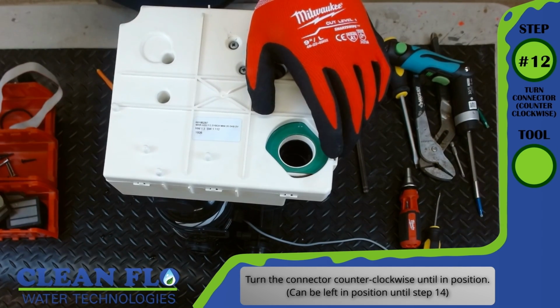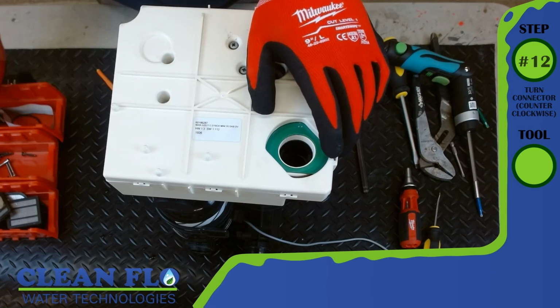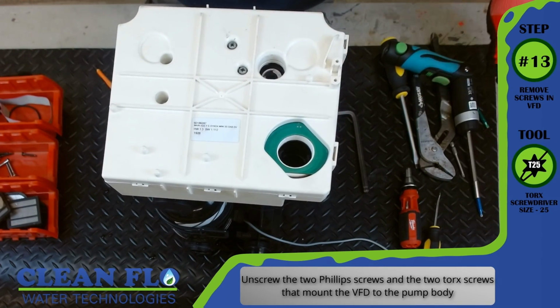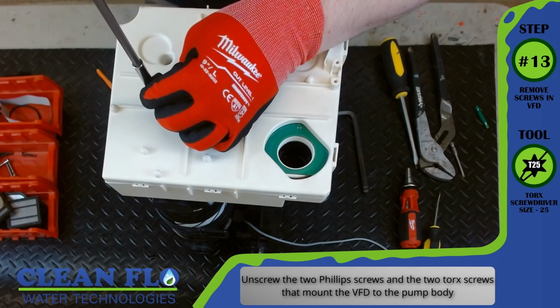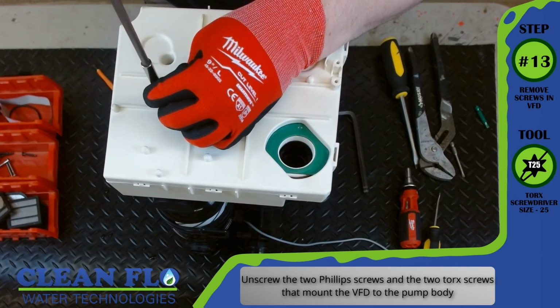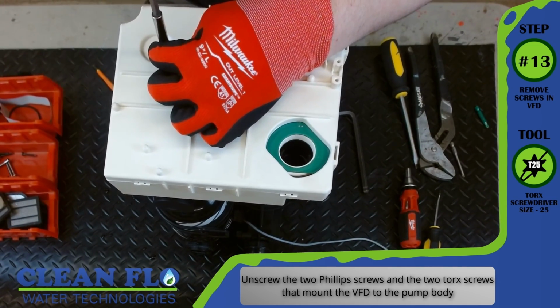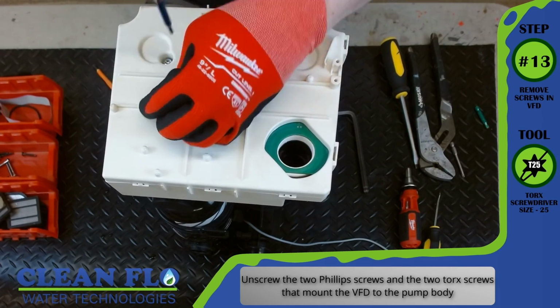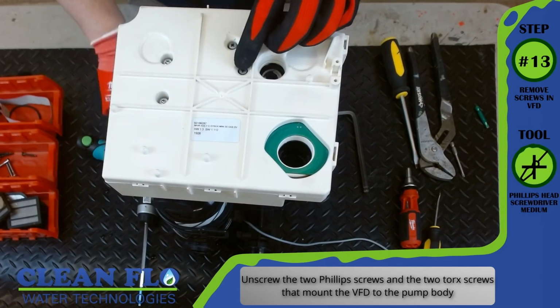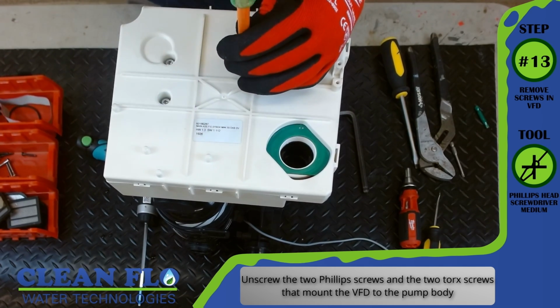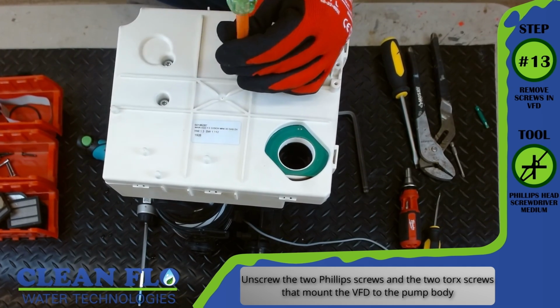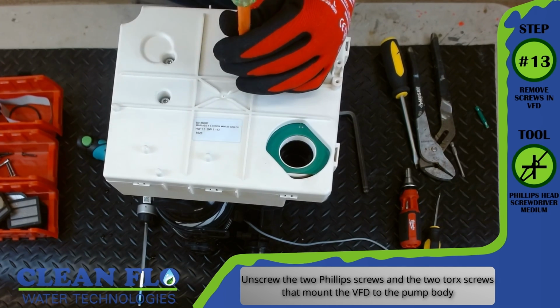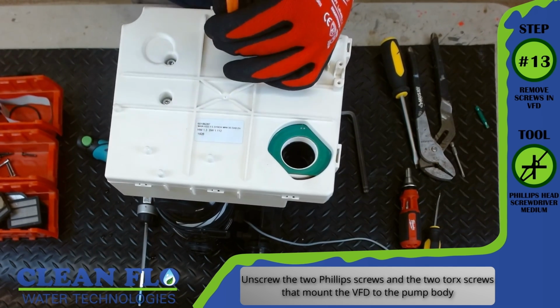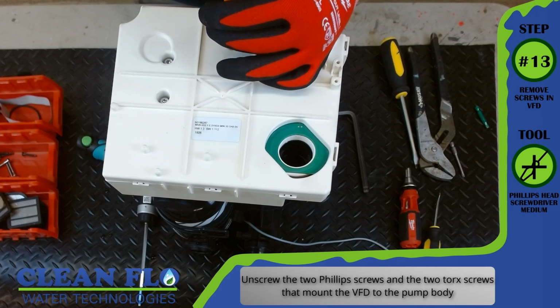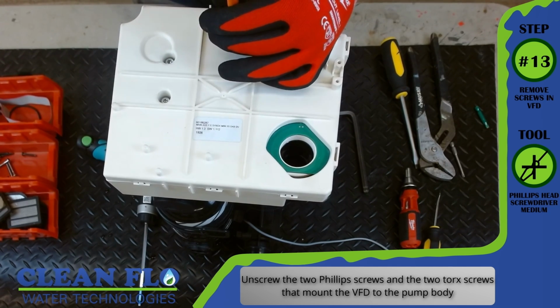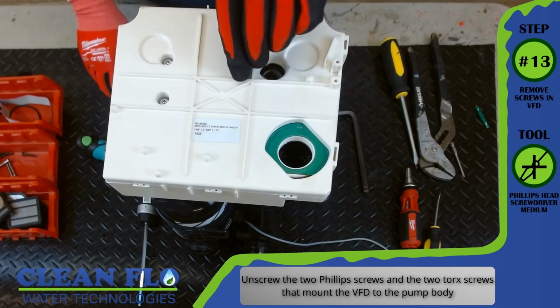Now I have removed the connector and put it in one of the bins. Step 13, remove the screw in the VFD. Tool, Phillips head screwdriver, medium. Unscrew the 2 Phillips screws and the 2 Torx screws that mount the VFD onto the pump body. Now both a Phillips screwdriver and a Torx screwdriver are required for this step. These screws actually mount the VFD to the pump assembly and actually to the motor itself. Inside this white casing is the variable frequency drive for the pump.